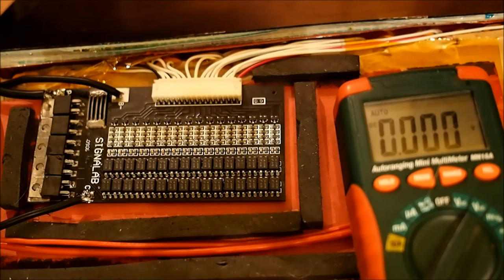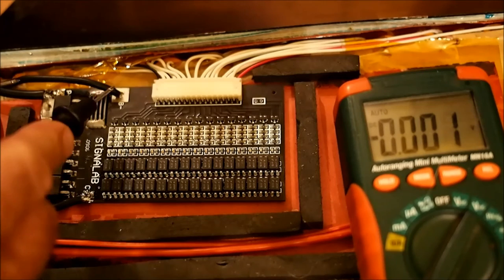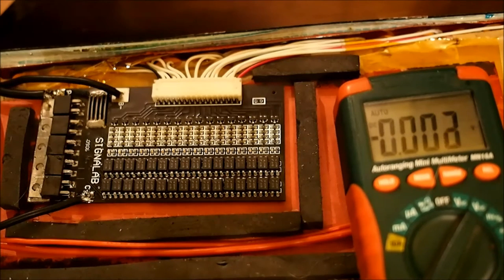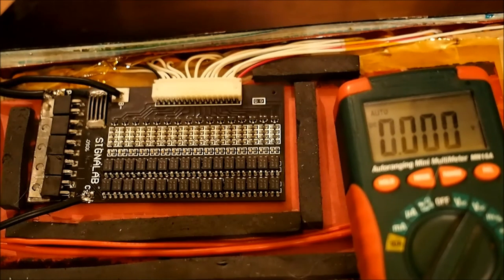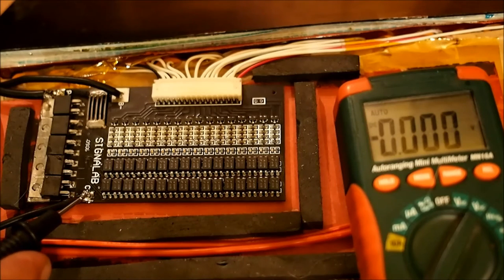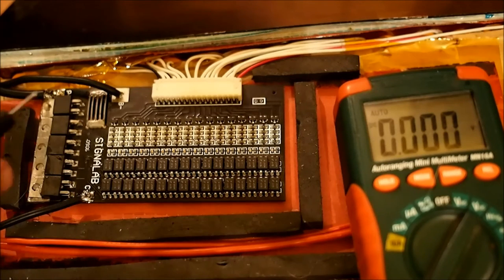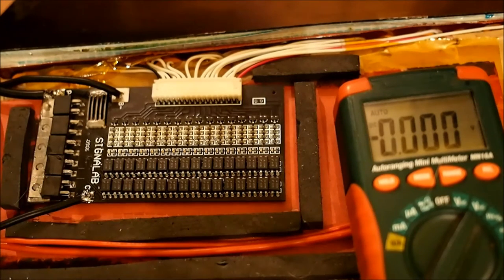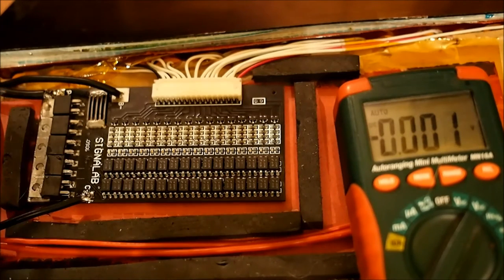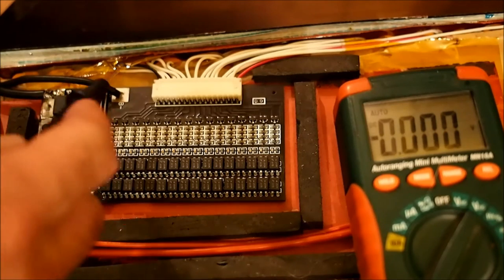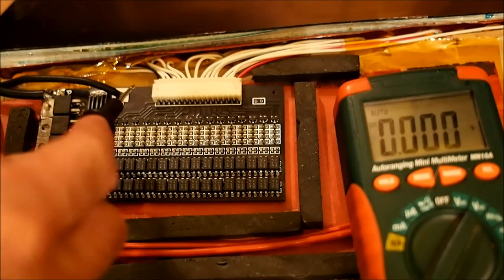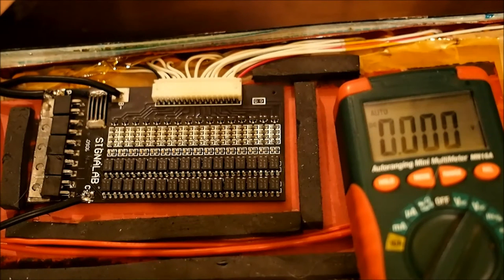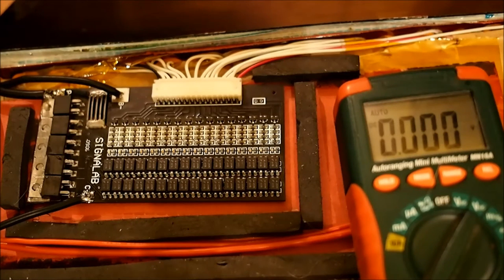If you see any voltage between any of those, that's a bad sign and tends to indicate a problem. If you see voltage between the charge and the battery or charge and this, that means you've got a problem with your charging circuit. If you see voltage between those two points, there's something going on with your discharge circuit and something is wrong and further troubleshooting is going to be required.